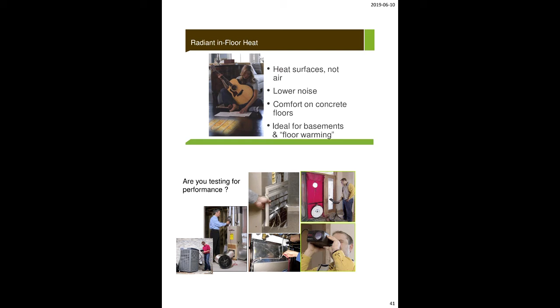The other thing is testing. Again, if you haven't done testing, I'm not just talking blower door, I'm actually going to show you these other things on the mechanical side. Testing static pressure in your system. It takes all of 5 minutes for somebody to check the static pressure in a forced air system. If you don't have enough static pressure, you don't have enough gas in the tank to push the air through the rest of the house. It's the single biggest issue we're finding in the field.